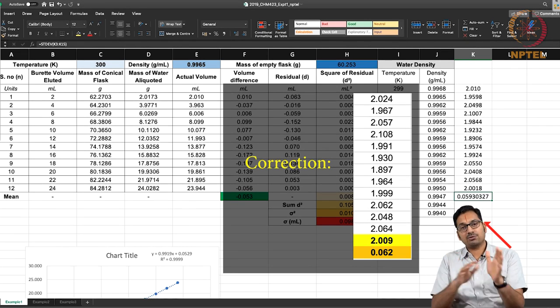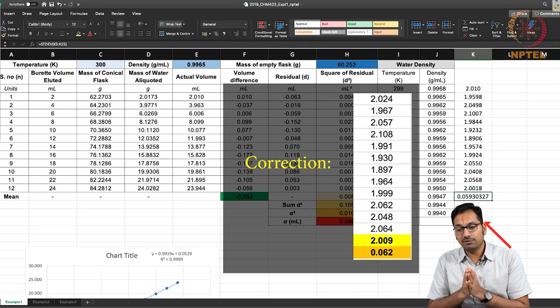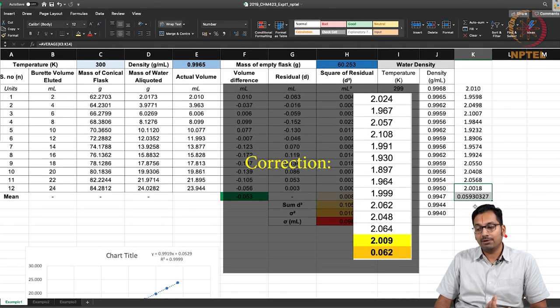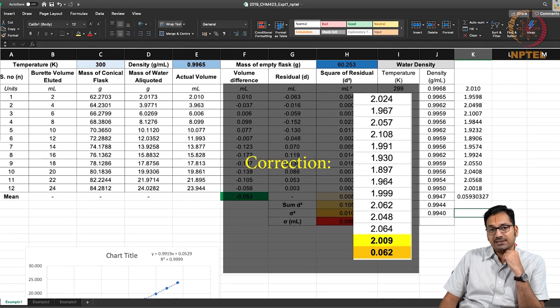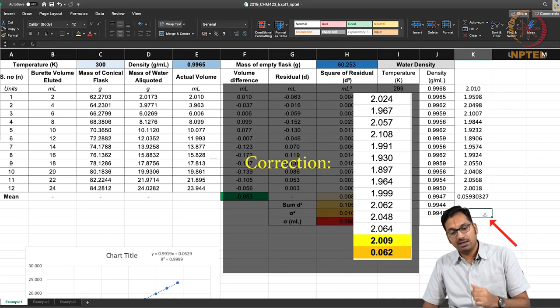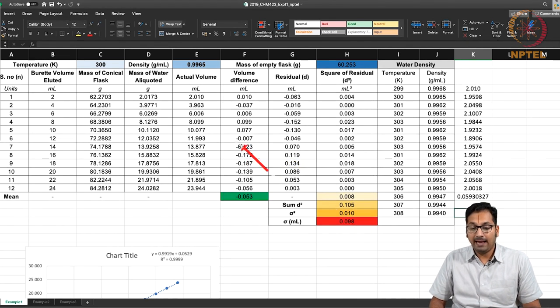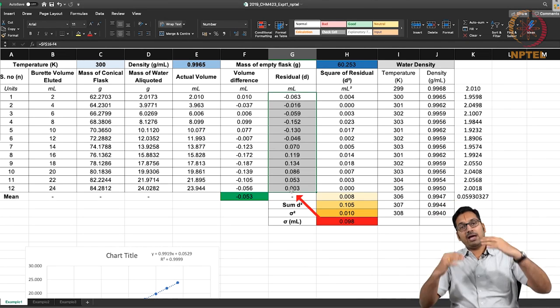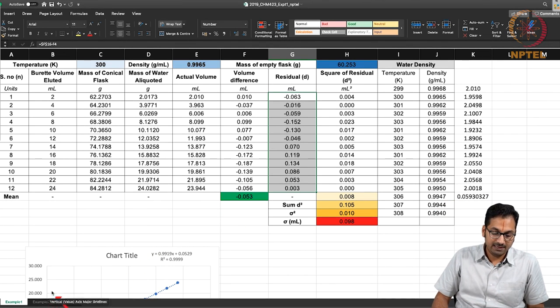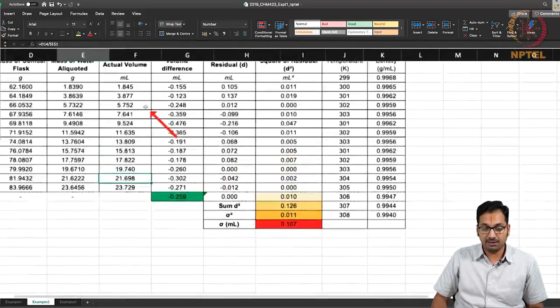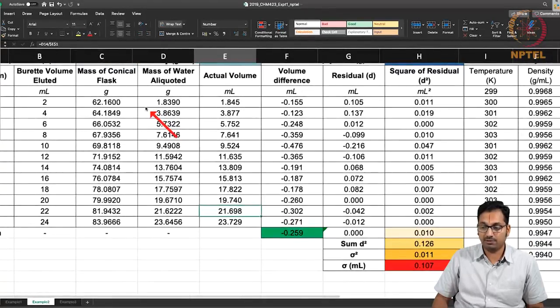You are able to realize the same analysis could be done in subtly different ways giving subtly different values. But overall, you had a 2 ml target and you are indeed getting an average around 2 ml, with a standard deviation of about 0.06 ml. So you have a variation of 60 microliters in each aliquot. You are also able to remember that the residuals for each measurement are above and below the average, which is reassuring.